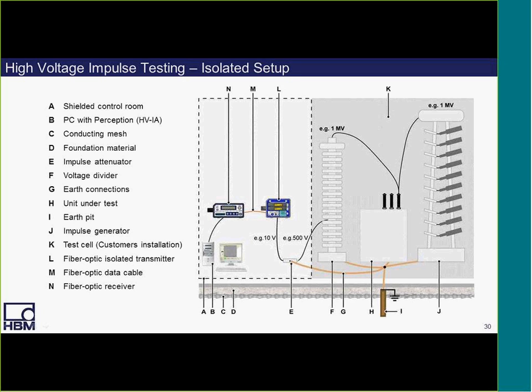So in this example, the advantages compared to a traditional test setup include no electrical connection between the test cell signals and the measurement equipment and PC powered in the control room. So this creates a safe environment for both the user and the equipment. There's also no equalizing currents between the test cell earth connection and the mains earth connection.